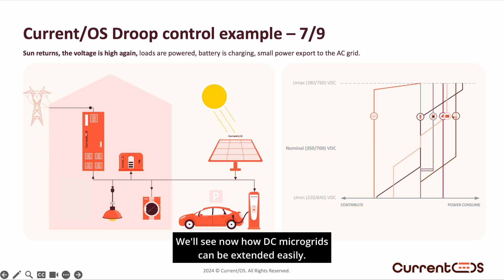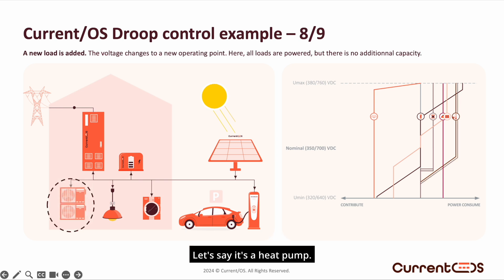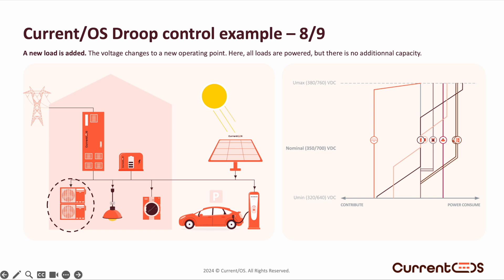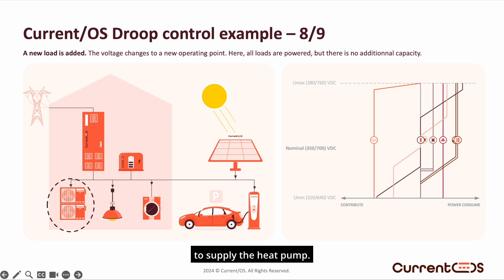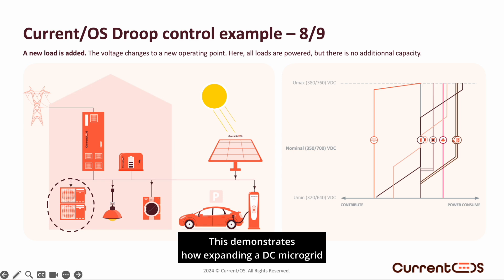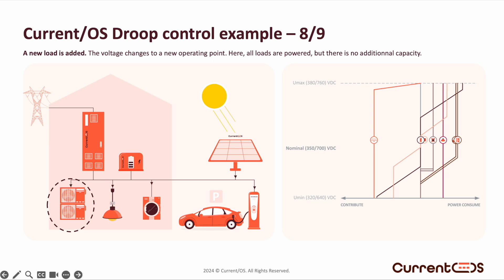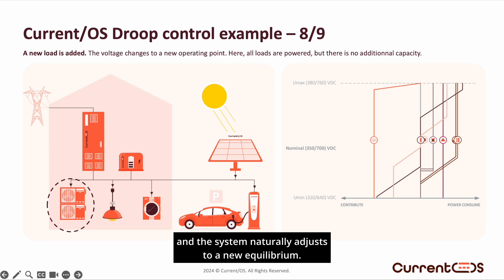We'll see now how microgrids can be extended easily. Let's add a new load similar to an electric vehicle in terms of nominal power, but for a different purpose — let's say it's a heat pump. In the theoretical diagram on the right, a new curve appears and the system finds a new equilibrium. At this point, there is no longer enough power to charge the battery or export to the grid, but there is enough to supply the heat pump. This demonstrates how expanding a DC microgrid with Current OS distributed control simplifies the process significantly. There's no need to adjust both the electrical and automation systems or involve multiple skill sets — the electrician simply connects the new device and the system naturally adjusts to a new equilibrium.